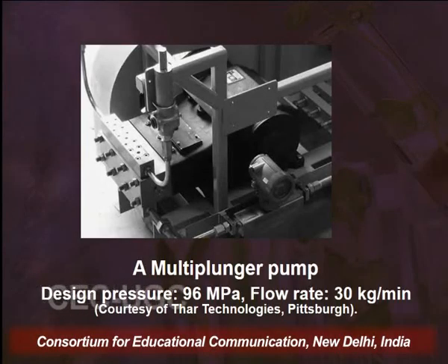So one has to be very critical in designing the pumps and the compressors, so that they can maintain the required pressure, the flow rate, and the temperature throughout the extraction process. Now in this picture you can see the image of a multi-plunger pump that is designed to a maximum pressure limit of 96 megapascal and a flow rate of 30 kgs per minute. This is an industrial scale multi-plunger pump that is used by an industry for a supercritical fluid unit.